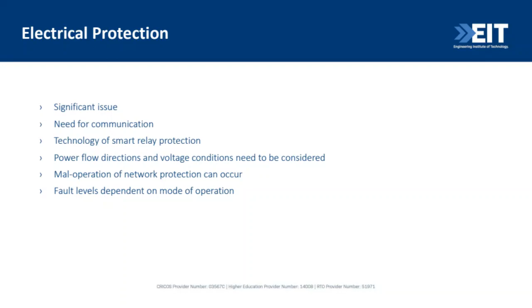Protection—oh, that's a nightmare. Nowadays, protection without communication has no meaning, so you need adequate communication. Protection and communication go hand in hand, because you have to communicate the protection state to other parts of the system. You need technology with smart relay protection, since we have smart grids, so the protection must also be smart. Power flow directions and voltage conditions have to be considered, mal-operation of network protection can occur, and fault level dependence on mode of operation can occur.